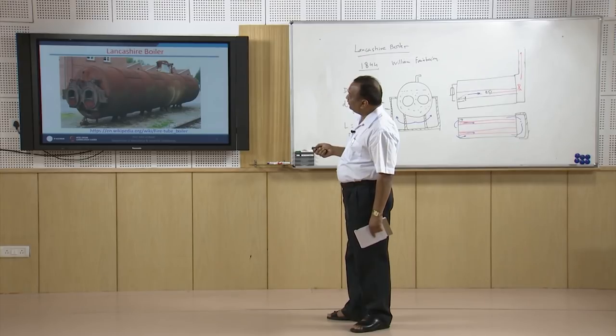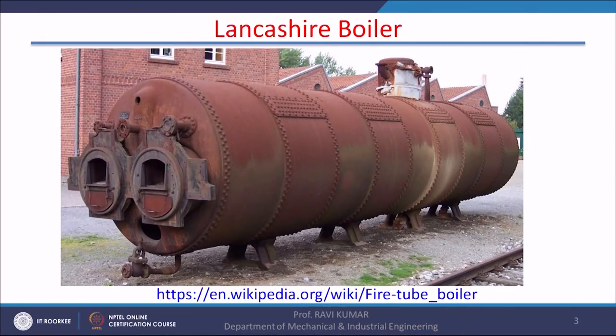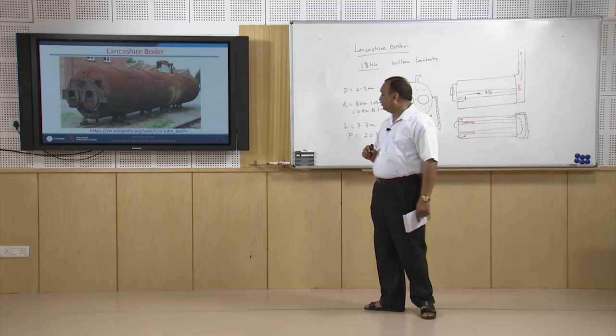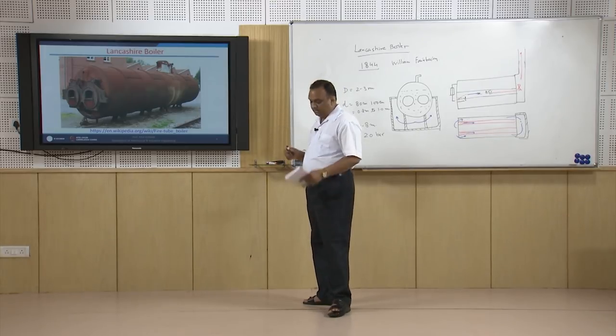The flue gases pass through these two tubes through the boiler — only the iron part of the boiler is shown here, brick masonry is not shown. Then the flue gases from the other side travel from the bottom of the boiler, come to the front, bifurcate, go sideways, and from the other side of the boiler leave from the chimney. This is the total movement of flue gases inside a Lancashire boiler.